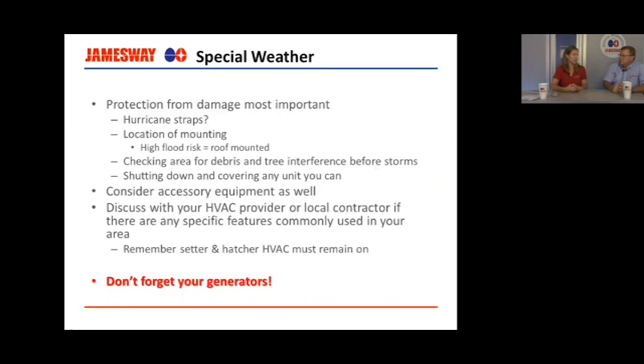But dehumidification is the biggest concern. But we can also do kind of cheap, costly to operate, but cheap retrofits. If you need to get through the next 5 years with that unit before you replace it, we can add something like an electric duct heater to provide the reheat that you need for dehumidification, as long as you have that excess cooling capacity so that we can subcool the air and then heat it back up to our room temp.